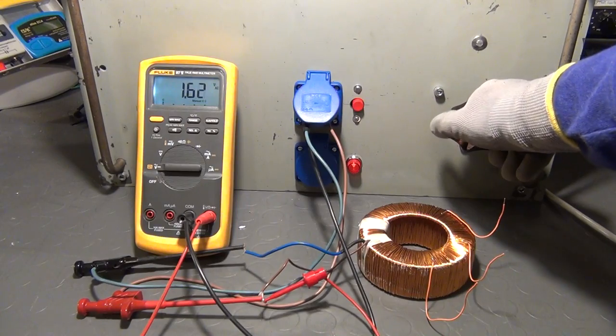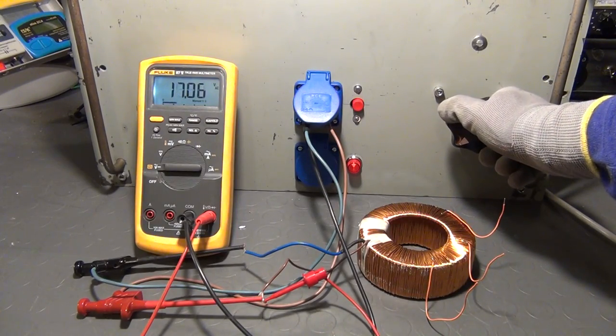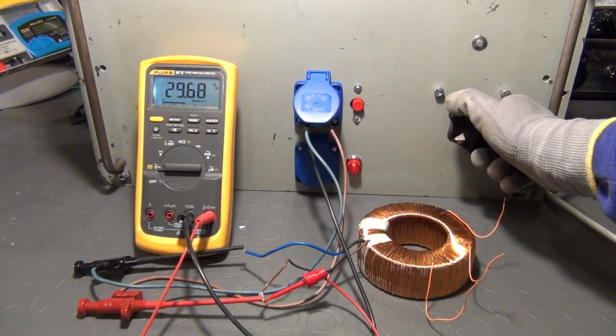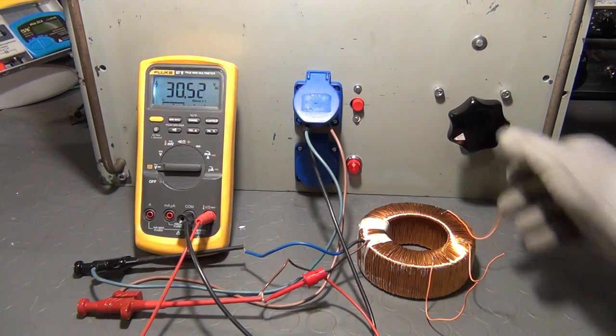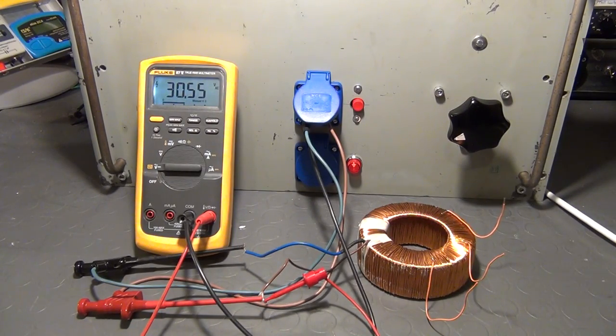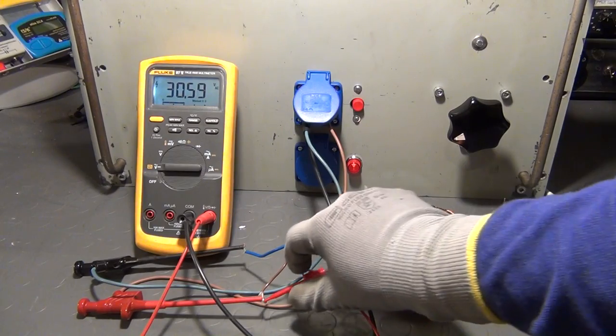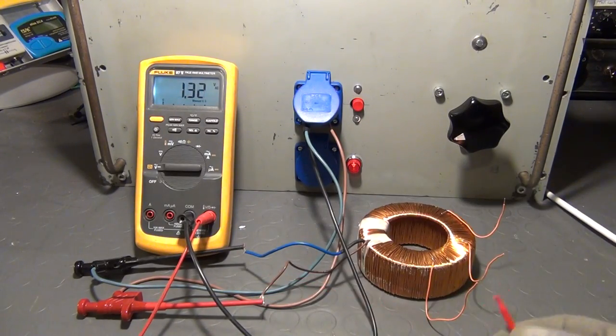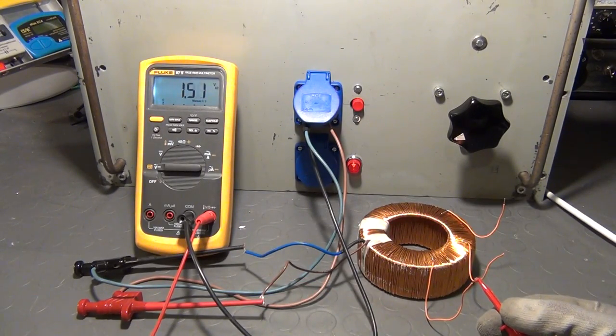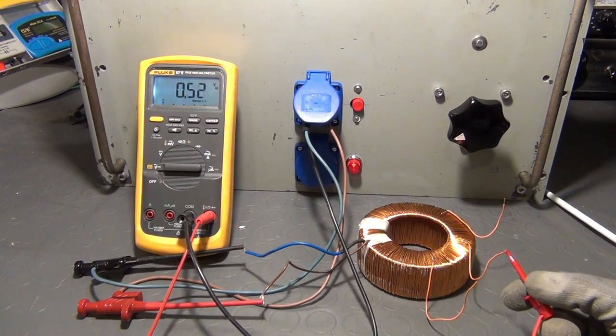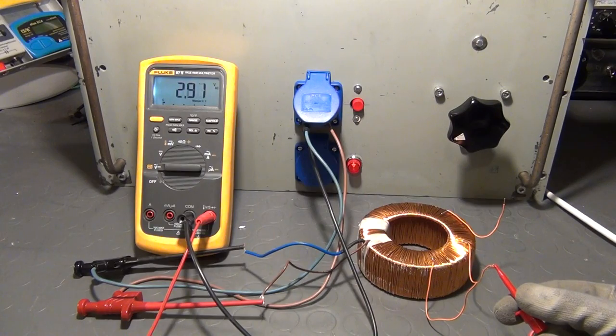To test it, I connect it to my isolation transformer unit. Instead of supplying it with 230 volts, I supply it with just around 30 volts. This way you can use the unit to test all kinds of transformers relatively safely. And as you can see, the voltages at the 3 taps are all smaller than the supply voltage itself.